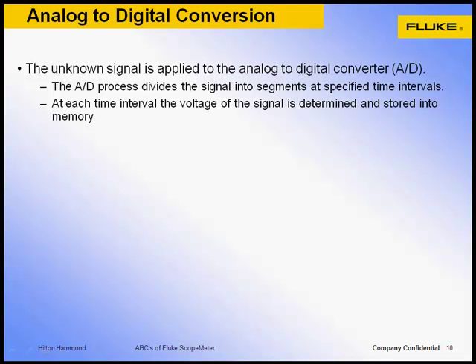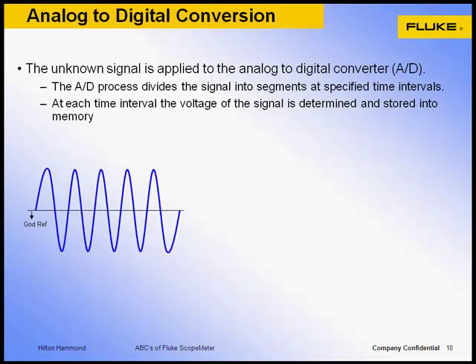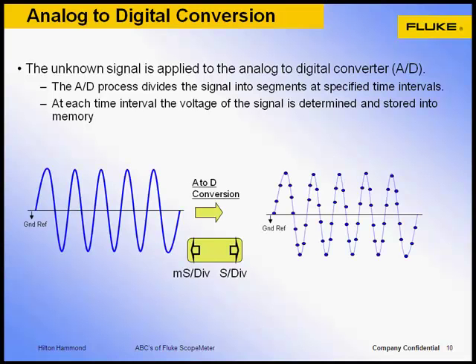As we have already discussed, an oscilloscope uses high speed analog to digital conversion technique to sample the unknown input signal. The objective being to digitize the unknown waveform as fast as possible. The faster the sample rate, the higher the horizontal sample resolution. Some errors can occur due to undersampling the waveform. First, aliasing. Say for example, if you only sample a sine wave once or twice per period, the resultant displayed waveform will look very different to the original sine wave. Perhaps more like a triangular wave.